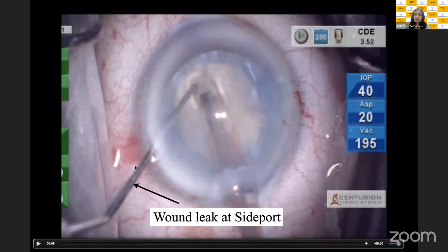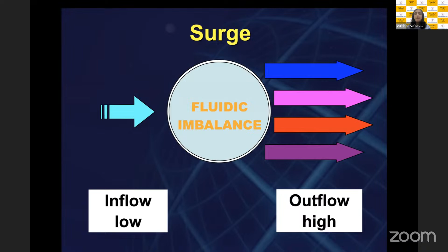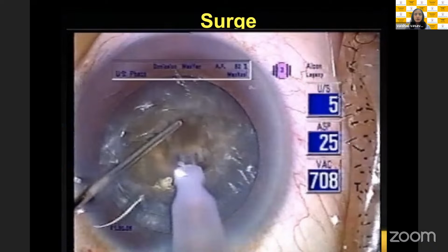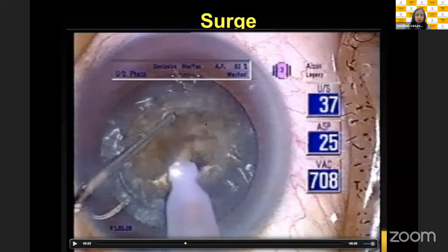Now moving on to a very, very important parameter in surgery, that is surge. What is it and how does it happen? Surge happens when there is sudden high outflow and the inflow cannot match. So the chamber collapses or fluctuates. That is basically surge, and it's nothing but fluid imbalance. And here you will see when that happens. Notice the vacuum is 700, the flow rate is 25 cc per minute, and the ultrasound is about 40. So this is an extreme level of surge.